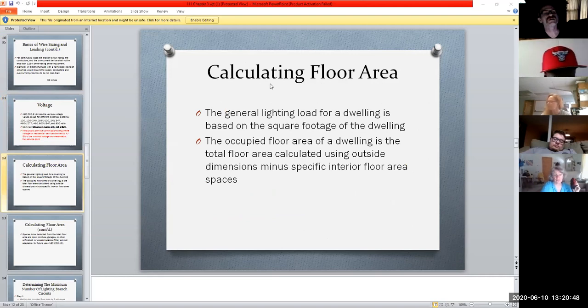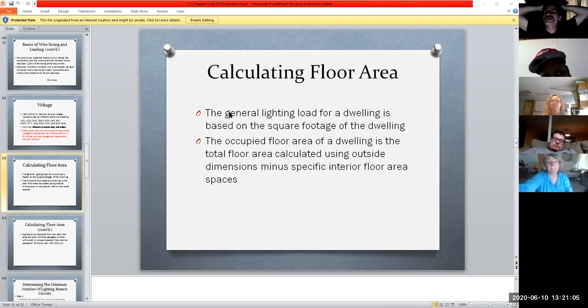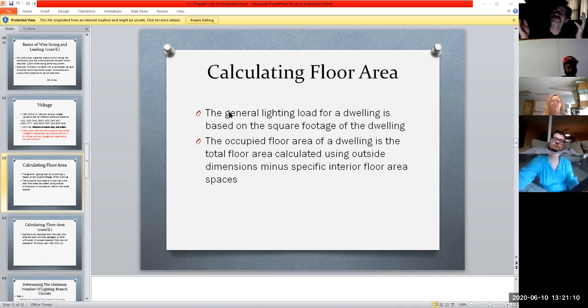So we'll look through chapter 3 and see how we size stuff. You've seen that the lighting circuits are based on the square footage of your house. Usually that's how they do the general lighting load, unless you have a few exceptions, where maybe in a room you have a ton of can lights. Then you would have to consider another factor, because you have more than the required amount of lighting that typically goes into a room. That would be considered a separate factor. But on average, you would just take your overall square footage of your house and plug it through and determine how many lighting branch circuits you're going to need in that house.